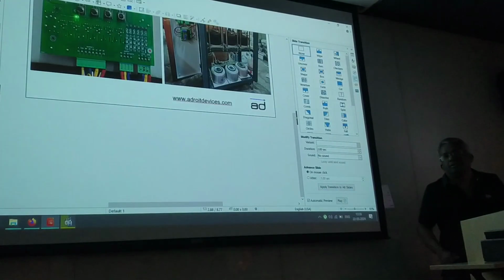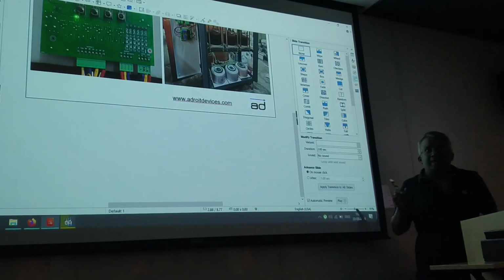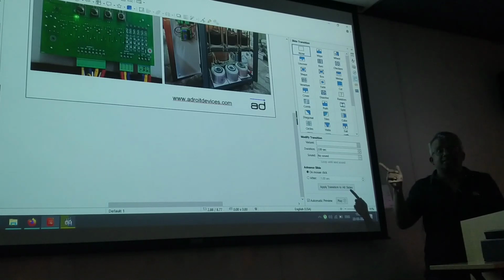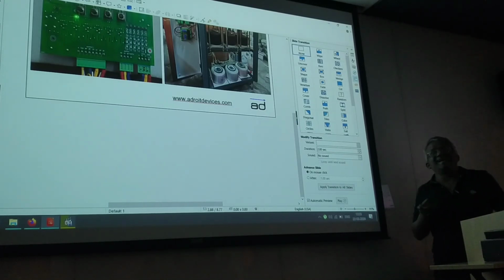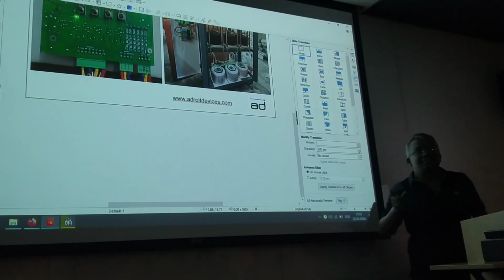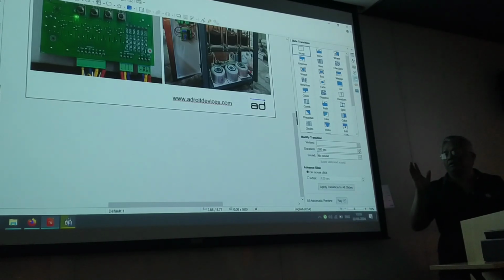Can you not use electronics for this? Yes, you can. But then it will be much faster than this, and cheaper too... no, actually it will be exorbitantly high, because here we are talking about 100 kVA kind of loads. If the load is less than say 5 kVA, then it might be somewhat on par, but when the loads become very high, these kinds of mechanical systems rule the roost.